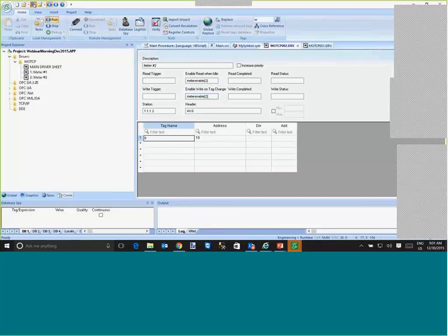So literally by writing zeros or ones in those tags, meter enable index 1 to 48, you can enable and disable the communication with each one of the 48 meters dynamically during the runtime, and you don't have to delete add devices every time. Okay?